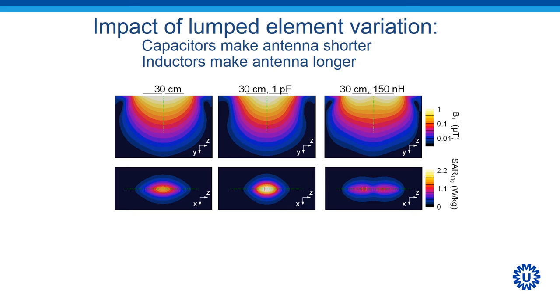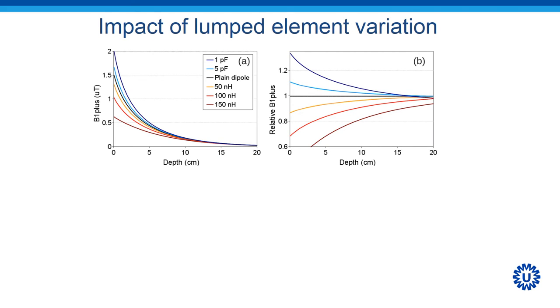If we take a look at the field distributions of such an antenna, we can see that the capacitor in between the segments actually shortens the effective length of the dipole, whereas adding inductors between the segments lengthens the effective length of the dipole. If we look at the profiles along the green dashed lines, we can see that the capacitors enhance the B1 plus field, whereas inductors reduce the B1 plus field.